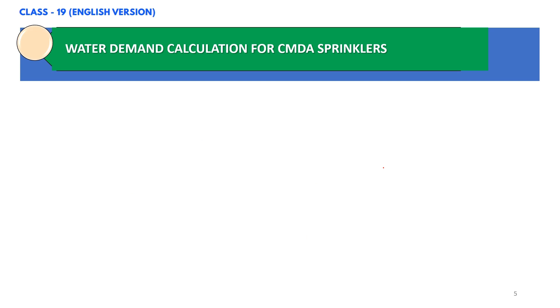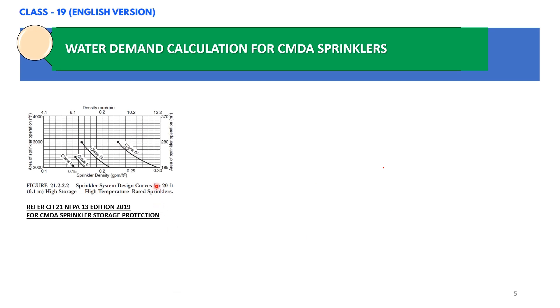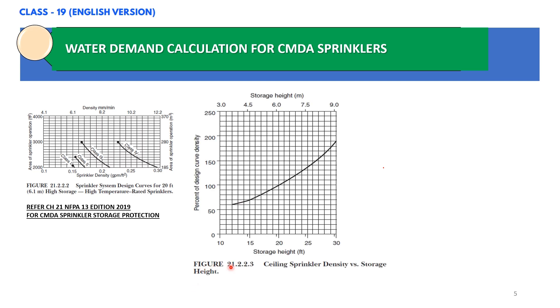So we determine the density and area from this graph for Class 4 commodity: that is 0.3 gpm per square feet and 2000 square feet area of sprinkler operation. Now we will adjust the density by using figure 21.2.2.3. On the x-axis it shows storage height in feet and on the y-axis it shows percent of design curve density. So we will adjust the density — I will just show it to you.